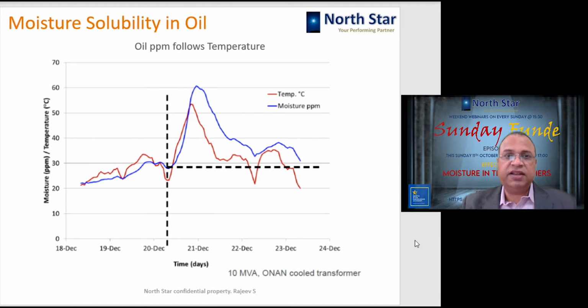So this graph is showing you the moisture solubility in oil. The blue colored is the moisture ppm and the red is temperature. You can see here a period of almost 9-10 days of a 10 MVA ONAN cooled transformer. As the temperature is varying, the ppm is also following the same trend. So what does that mean? When the temperature is high, your ppm in the oil is also high, for the same amount of total moisture inside the transformer.